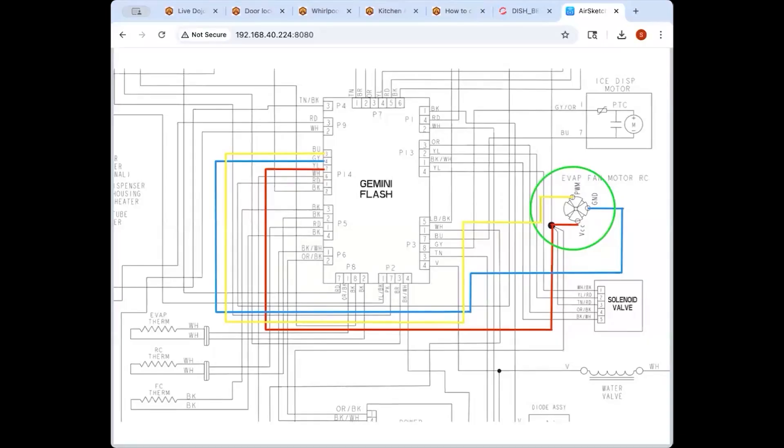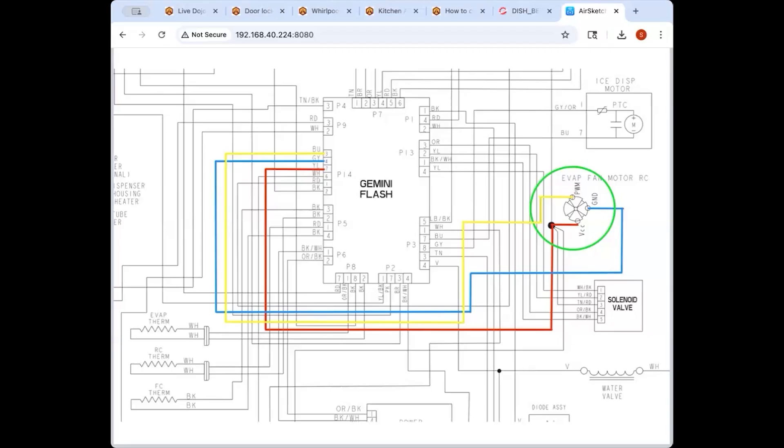And he could have, if he was unsure, he could have did another test, he could have did like a cheater test or something just for an extra measure just to give you more confidence. Nine volt battery. Yeah, you can say that cheater is another way of doing that. But in this case he didn't even need to cheater it because he had all good supply, all good inputs to that motor.